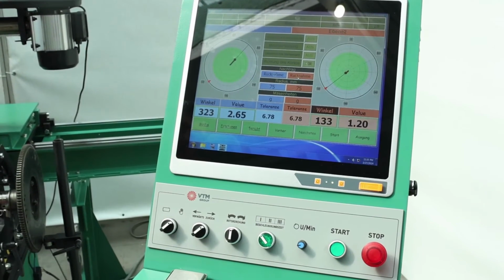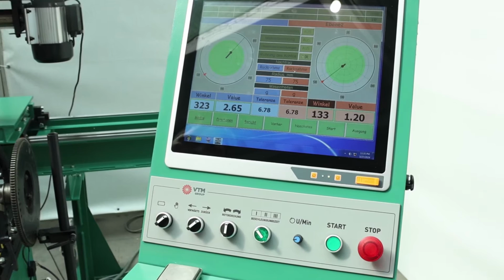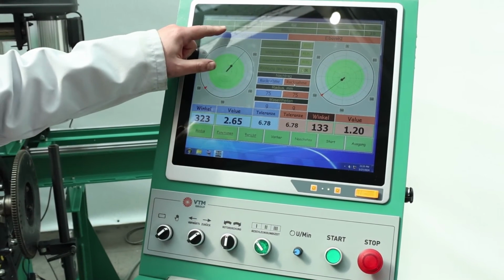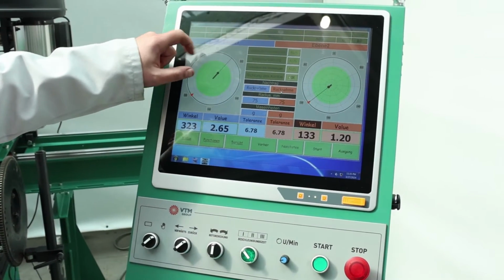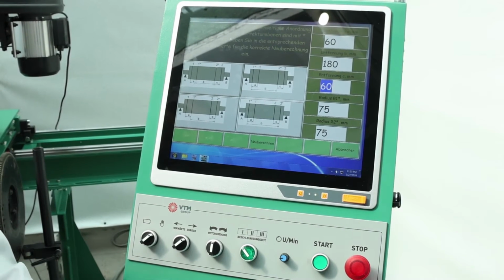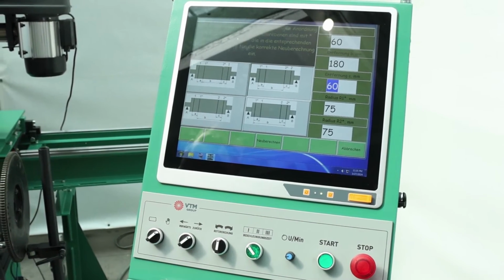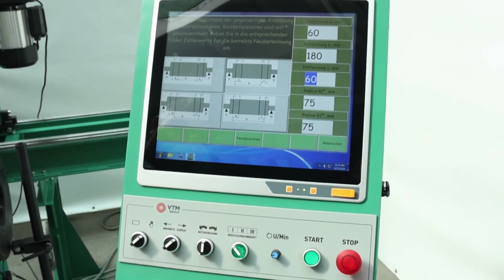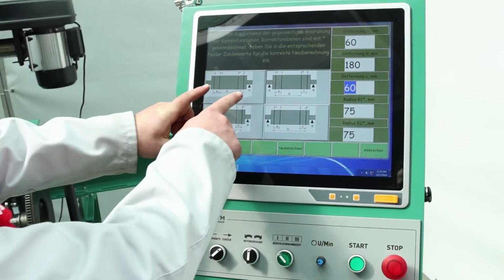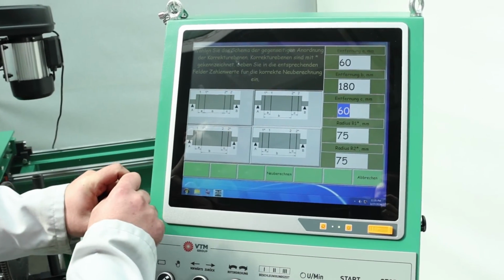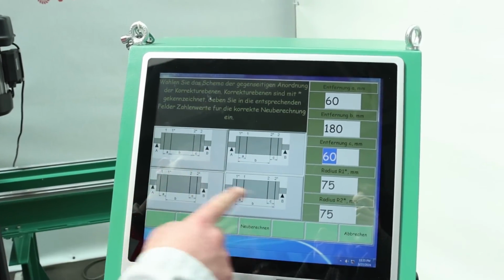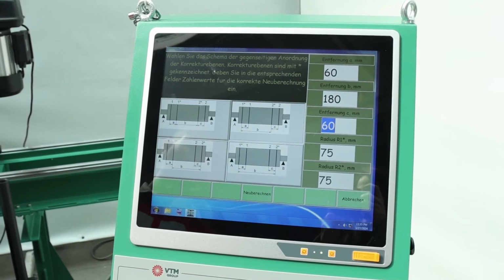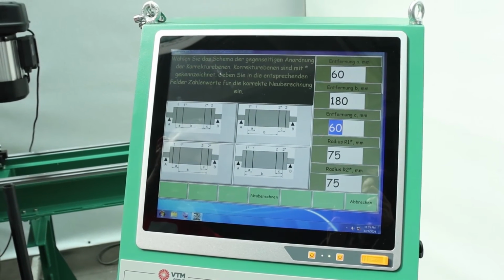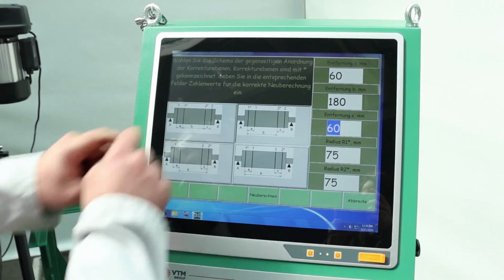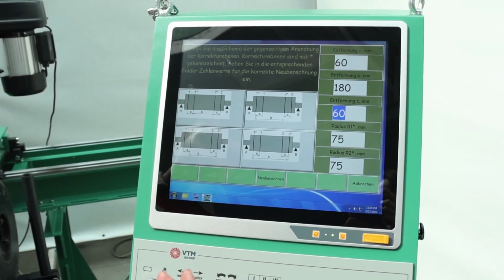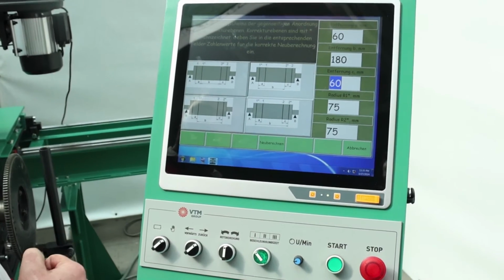The correction plane recalculation function will be useful for unbalance correction on the crankshaft. It is activated by clicking on plane 1. In this function, we can see that we have some correction planes, which are marked with numbers 1 and 2. We can also move them to 4 possible variants according to the scheme. New correction planes are shown with numbers 1 and 2 with an asterisk icon. We select the necessary picture to transfer to where we will transfer them.